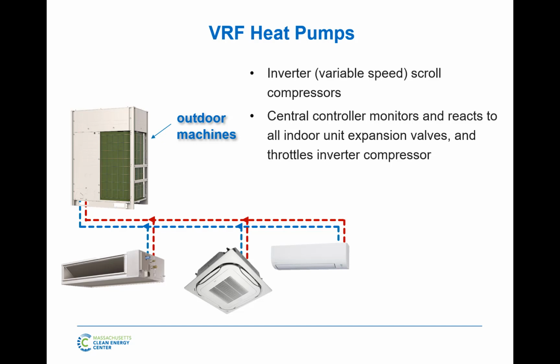That's VRF in about 3 minutes. That's the basis of it, and everything builds from that concept. There could be one compressor, there could be 2 compressors. Depends on the manufacturer, depends on the size of the machines, and they're going to stage each other, but each compressor is variable speed. So if you're at 50% load, it might run one of the 2 compressors at full speed and the other's off. Or a manufacturer might say, I'm actually more efficient running both compressors at 50%. They all do internally, they all optimize their technology that way.